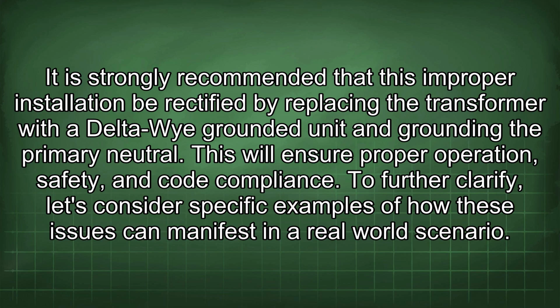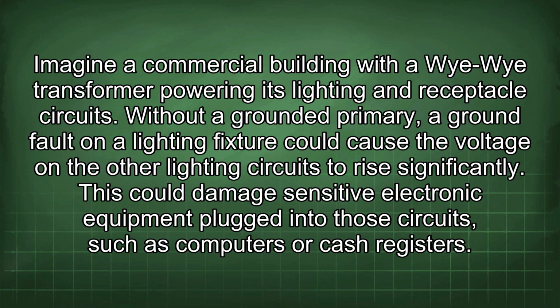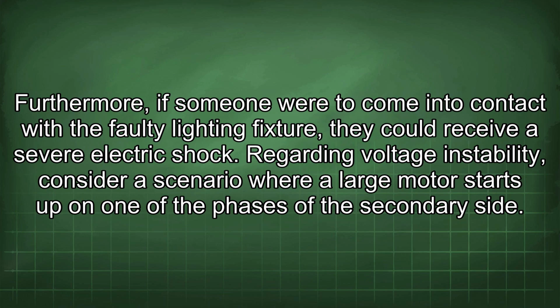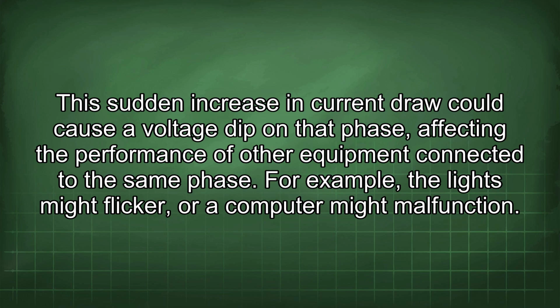To further clarify, let's consider specific examples of how these issues can manifest in a real-world scenario. Imagine a commercial building with a Wye-Wye transformer powering its lighting and receptacle circuits. Without a grounded primary, a ground fault on a lighting fixture could cause the voltage on the other lighting circuits to rise significantly. This could damage sensitive electronic equipment plugged into those circuits, such as computers or cash registers. Furthermore, if someone were to come into contact with the faulty lighting fixture, they could receive a severe electric shock. Regarding voltage instability, consider a scenario where a large motor starts up on one of the phases of the secondary side. This sudden increase in current draw could cause a voltage dip on that phase, affecting the performance of other equipment connected to the same phase.